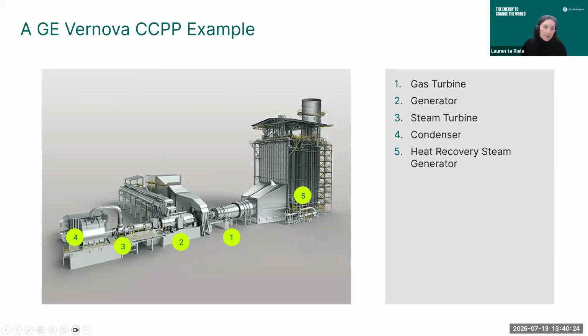This is where the boiler exists, as I said. We call this the heat recovery steam generator, or HRSG. This is a very giant heat exchanger with tons of coils of water that is boiled and pressurized. That boiled water comes all the way over to our steam turbine, where it is expanded to generate more power and then goes to our condenser.